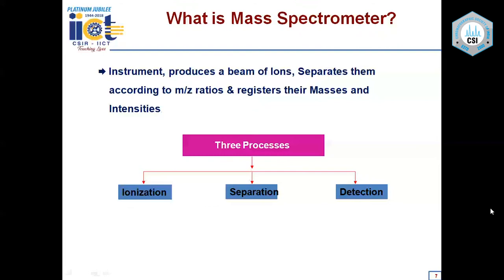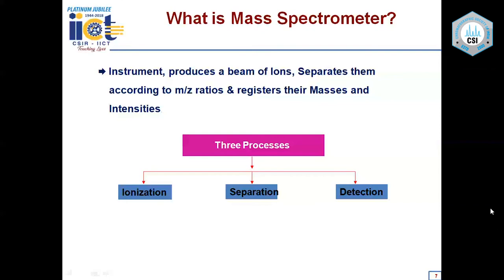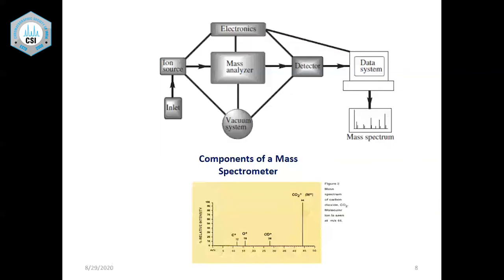A mass spectrometer produces a beam of ions, separates them according to mass-to-charge ratios, and registers their masses and intensities. Three processes take place: first, ionization — neutral molecules are converted to ions; second, ions are separated by the analyzer; and third, they are detected. The inlet is how samples are introduced into the source. Solid samples are introduced using a solid probe with a quartz crucible via a vacuum interlock, since mass spectrometers are maintained at very high vacuum.